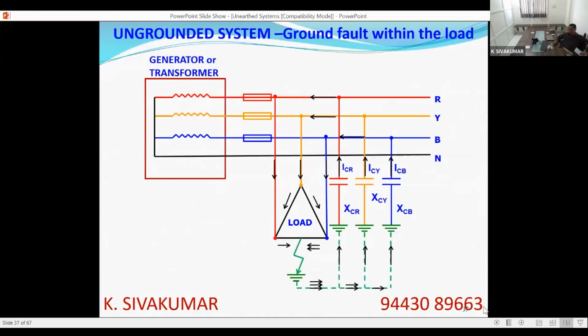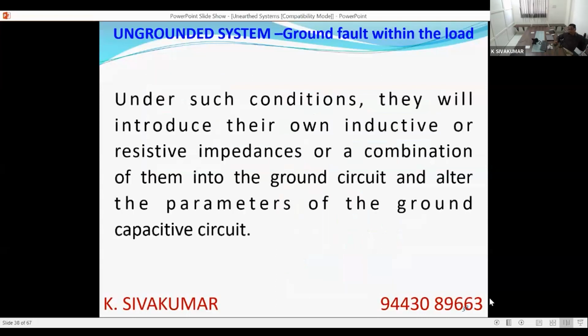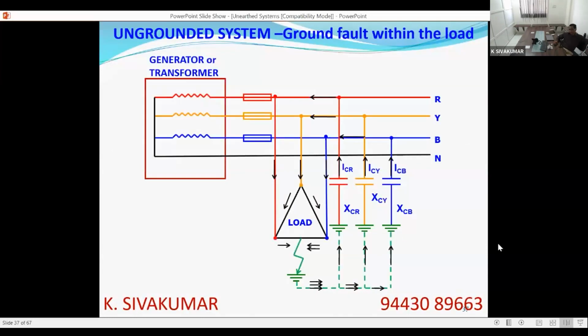This is a network, there is a source and there is a load. If you can see, one winding of the load has an earth fault. You can see the direction in which the current flows. There will be ICR, ICY, ICB, and through the load there will be current flow. The capacitors will charge and discharge through the load. Capacitors will feed into the fault through the load now. Under such conditions, they will introduce their own inductive or resistive impedance or a combination of them into the ground circuit. Now it is no more only capacitive current. It will be a mixture. It will be a series circuit of R and C, or XL and XC, or R, XL, XC, depending upon the proportion of the components.